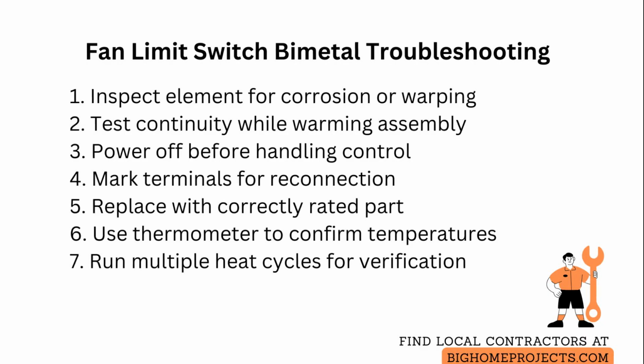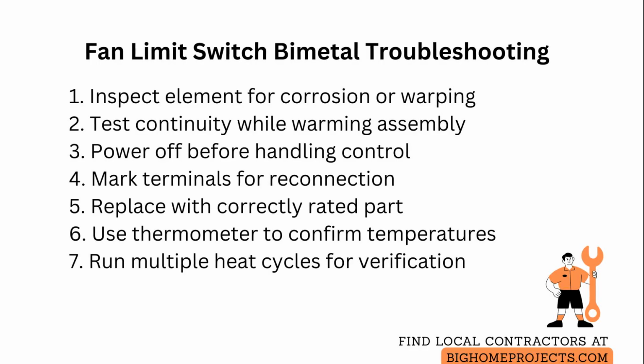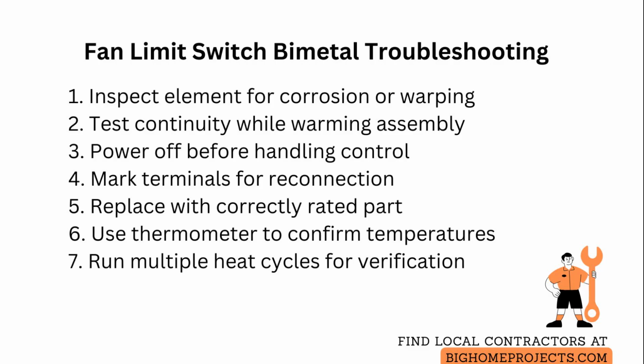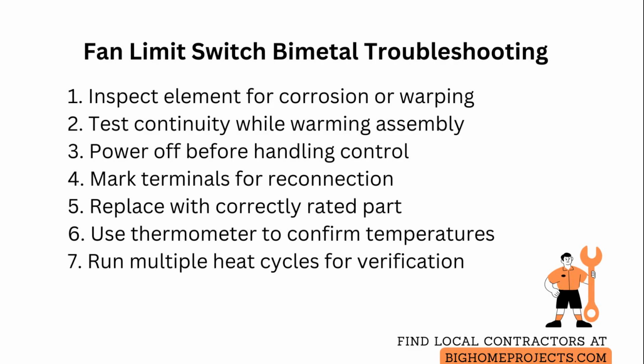After replacement, run several heat cycles and observe consistent fan start and stop points and verify the heat exchanger cool down behaves predictably to ensure the new control interacts correctly with the furnace limit system.